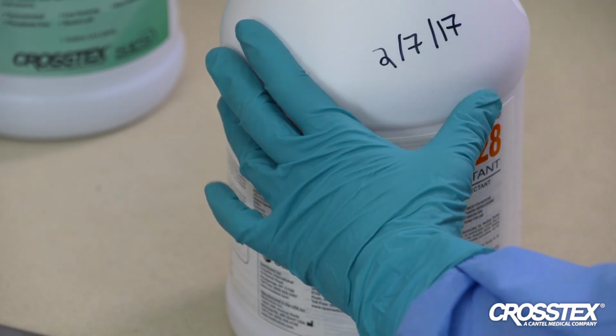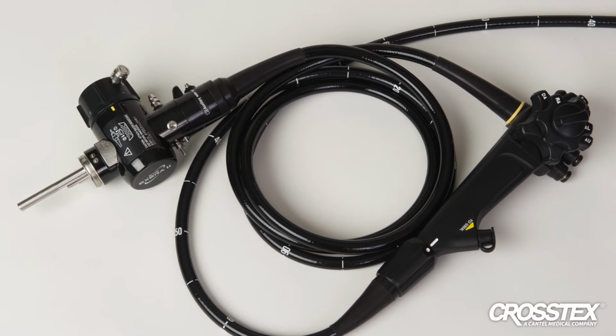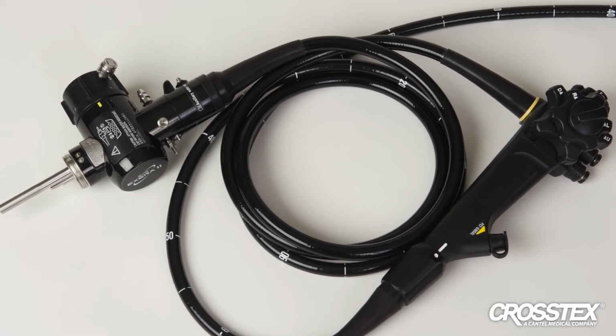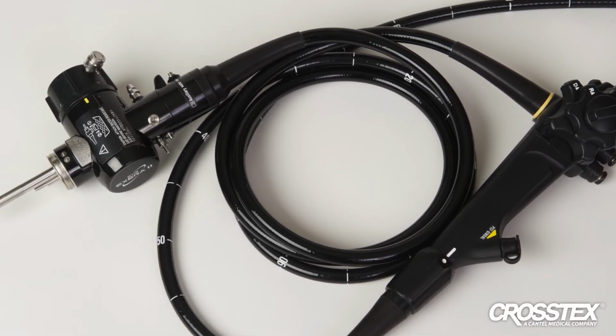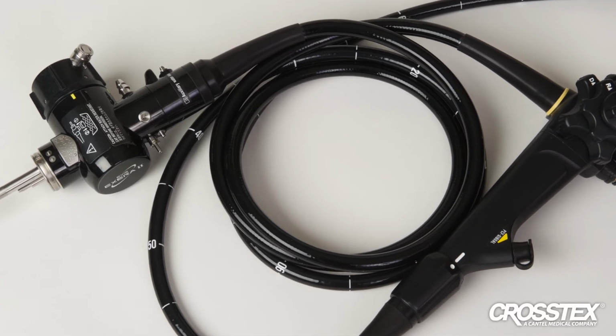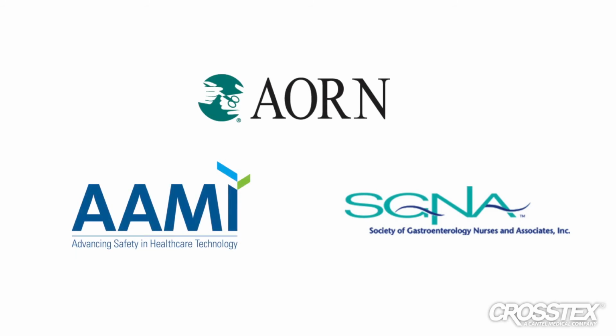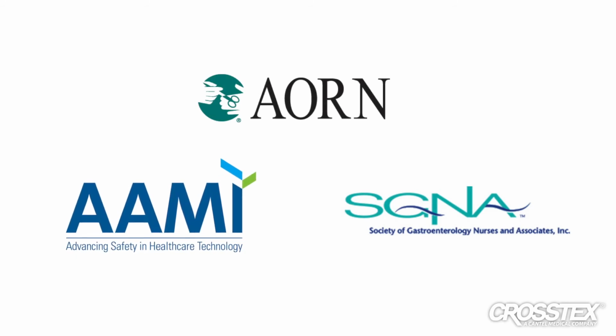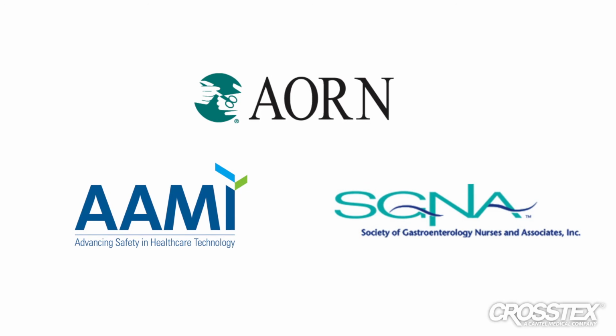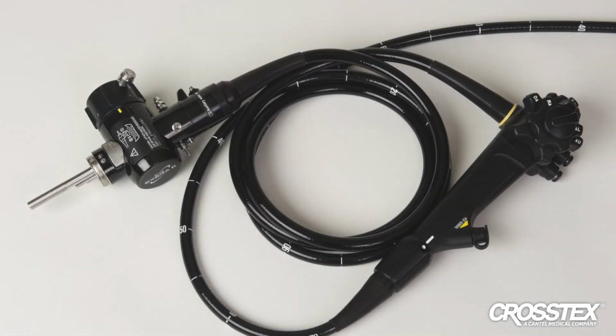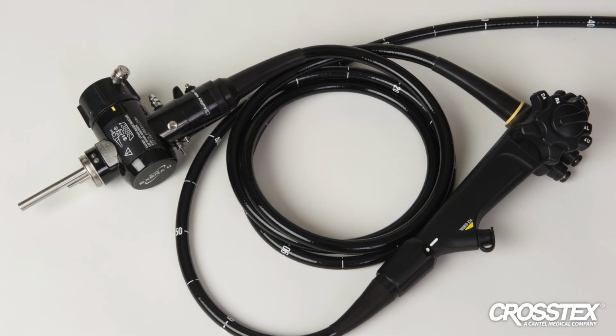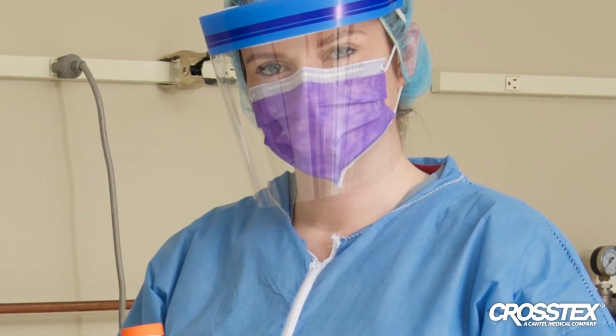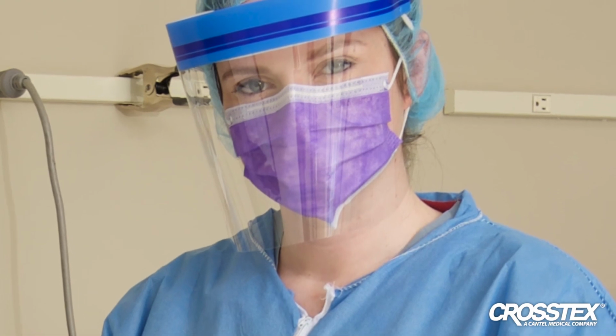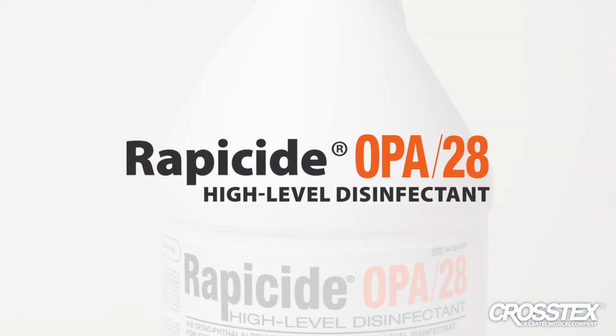Flexible endoscopes are some of the most challenging medical devices for healthcare facilities to reprocess due to their unique design and complex reprocessing steps. But through strict adherence to standards and best practices, such as those set forth by AAMI, AORN, and SGNA, healthcare facilities and those responsible for the reprocessing of heat-sensitive semi-critical medical devices can feel confident that quality and patient safety will not be compromised when using Rapicide OPA 28 high-level disinfectant.